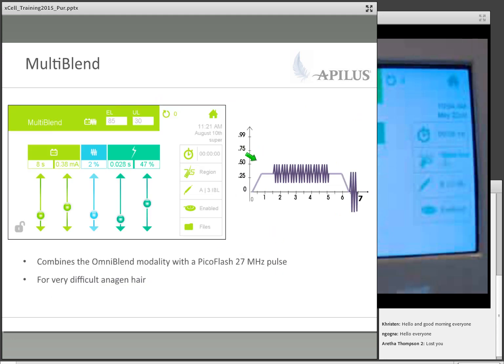The Omni blend on steroids would be your multi-blend here. So the multi-blend starts off just like the Omni blend was. So if you ignore this last pulse here, you have exactly what you had with Omni blend. Again, when you look at the first two sections here, this is our galvanic, 8 seconds, 0.38 mA. Then we have our Omni blend type of high frequency. We have just 2% and it's continuous. What multi-blend adds though is a pulse of Picoflash here at the very end of the pulse.